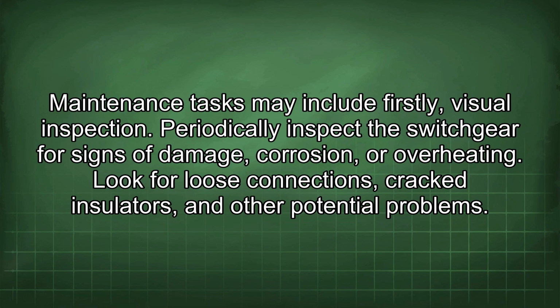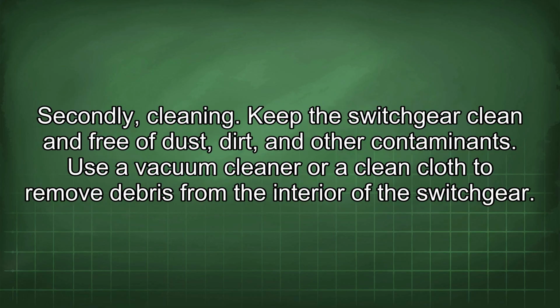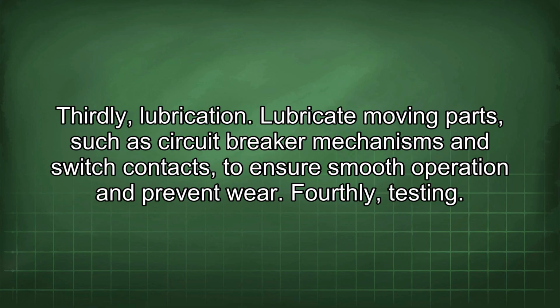Periodically inspect the switchgear for signs of damage, corrosion, or overheating. Look for loose connections, cracked insulators, and other potential problems. Secondly, cleaning. Keep the switchgear clean and free of dust, dirt, and other contaminants. Use a vacuum cleaner or a clean cloth to remove debris from the interior of the switchgear. Thirdly, lubrication. Lubricate moving parts, such as circuit breaker mechanisms and switch contacts, to ensure smooth operation and prevent wear.